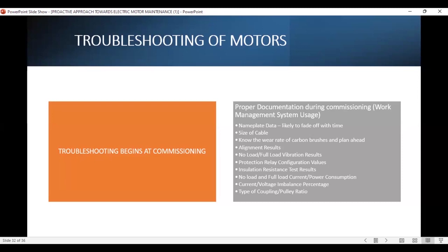Insulation resistance test results. During motor commissioning, the insulation resistance is tested. These results also show the strength of the insulation as the motor is being operated. So as you run and you measure it, you can compare it with the initial values to see whether you are losing your insulation or the insulation is intact. The no load and full load current also have to be taken. Motors normally have about one third no load current. So you have your no load current and you ensure that your no load current is okay, so that when you run on full load and there are issues, you know how to analyze your fault to identify the root cause of it.